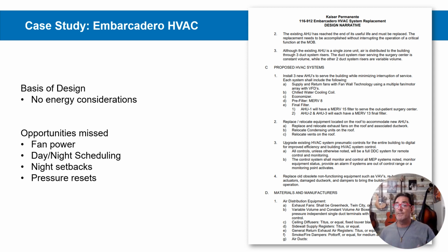There is a basis of design on this. They did submit a basis of design, but there's no energy considerations. There's really a lot of opportunities missed here, right? This is a hospital. It's a very high EUI building. So there were a lot of things that could have been looked at during design, and we just didn't look at them during design.